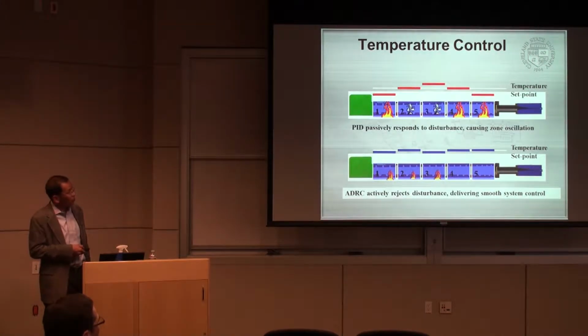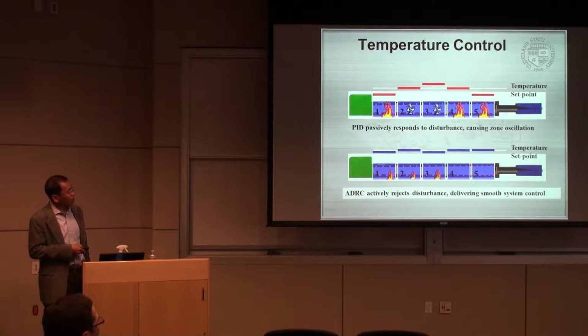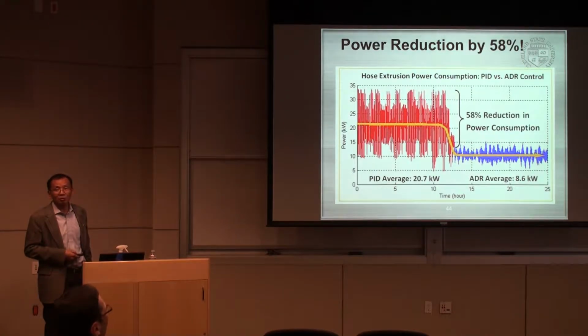Right? But once we put it in, look at this. The temperature fluctuation becomes much smaller. All the fans are turned off. Only 3 heaters remain active. The two other heaters are turned off. So that's why you see such a big change in energy consumption.